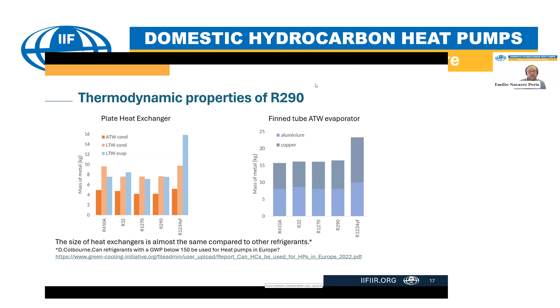And here, when we compare the discharge temperatures, we can see that the discharge temperature for propane is also significantly lower than the discharge temperature that we have with R32 or with R134a. This means that it is not complicated to find in the market compressors working with propane that are able to work at evaporating temperatures of -10 degrees, with condensing temperatures of 80 degrees, without requiring any kind of liquid or vapor injection in order to operate on those conditions.